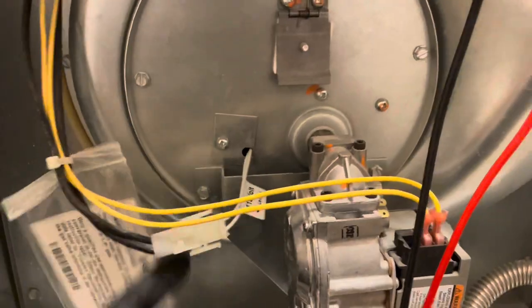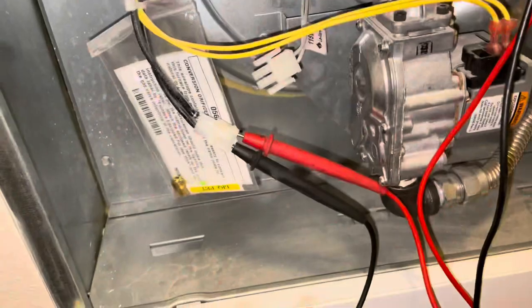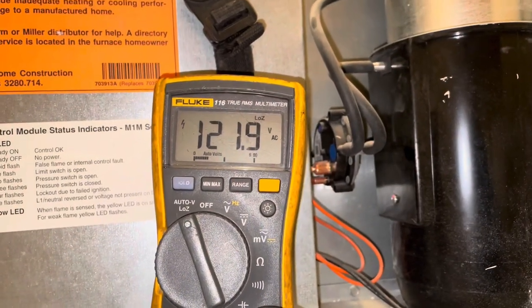All right, let's check voltage to the igniter. We're at 120, we're going to the igniter. Something on the board's doing the correct job.